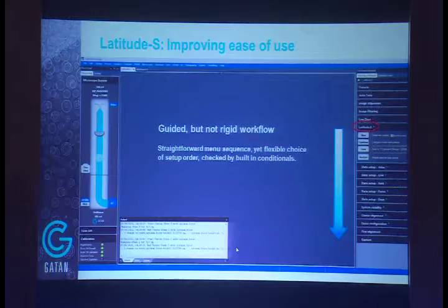And so the beam turns on and off, so you can get an indication of the status of the microscope. You can see on the lower left here, we have an indication of what's calibrated. Calibrations can change or go stale. And at every different magnification, you may need a calibration for something. And this will reflect in real time sort of what the status of your microscope is.